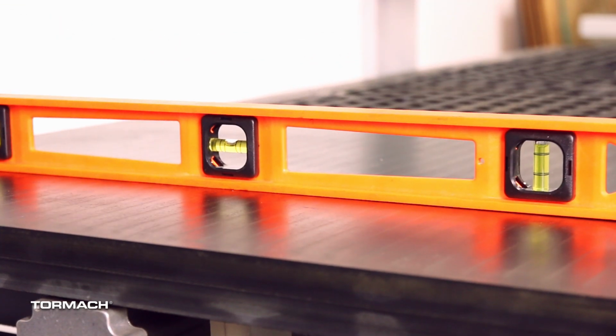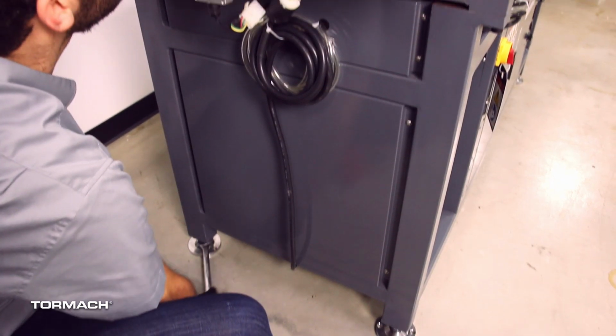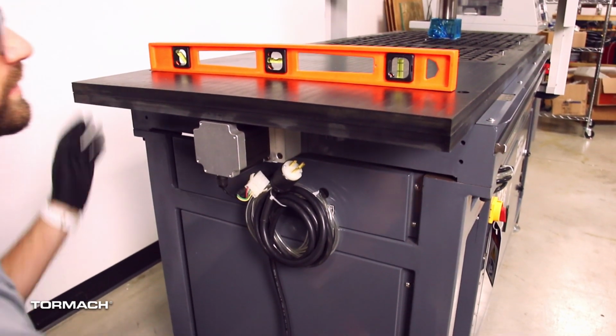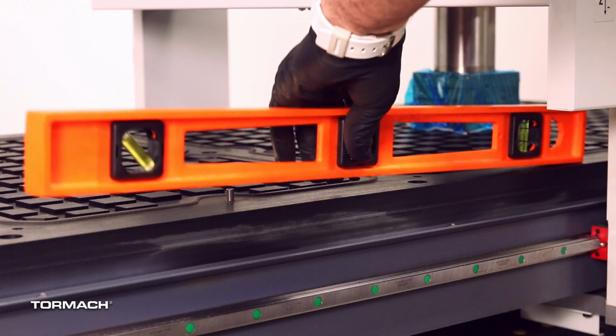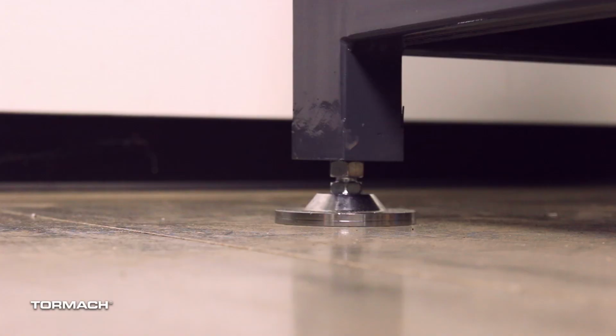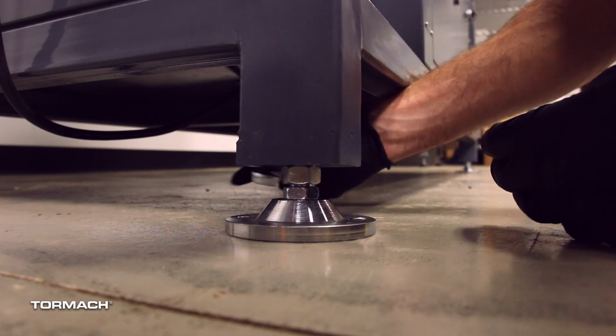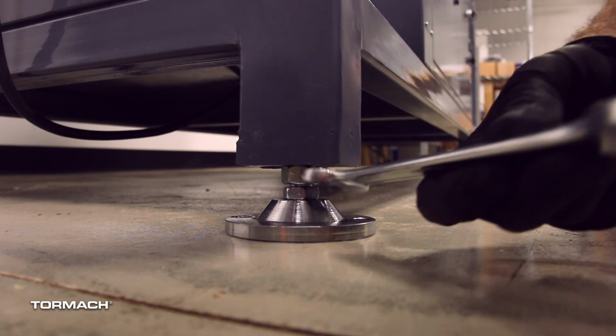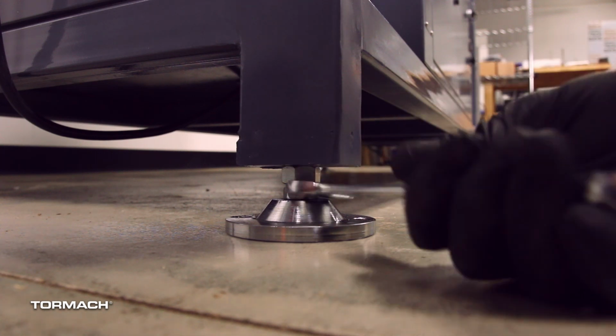Then, using a carpenter level, level it by raising or lowering each foot with a lower nut and a 22mm or adjustable wrench. Be sure to avoid the vacuum gaskets. Examine all 4 feet and verify that each foot touches the floor. Tighten the top jam nut with a 24mm wrench, locking the feet in their position.